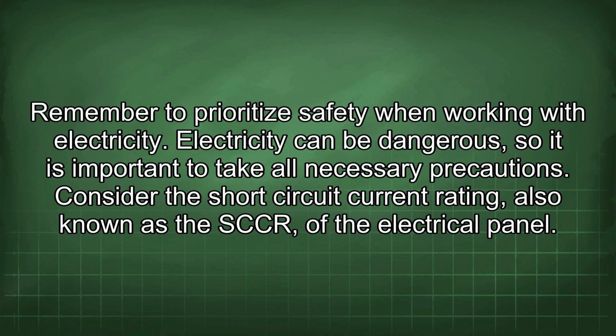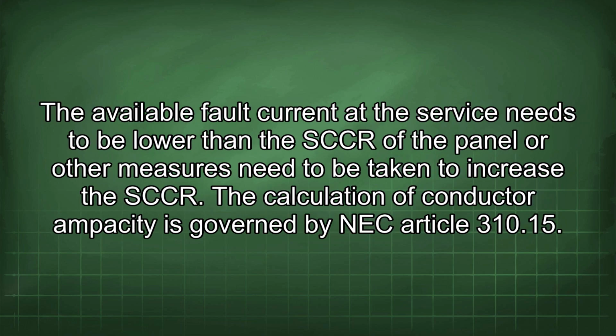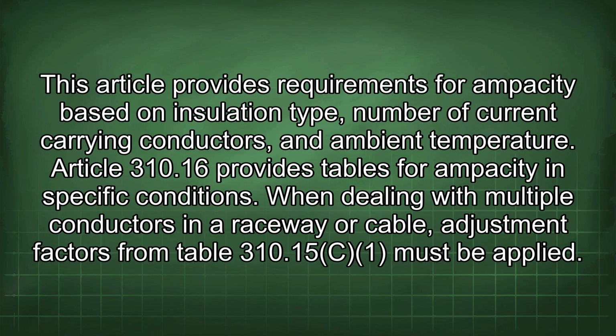Consider the short circuit current rating, also known as the SCCR, of the electrical panel. The available fault current at the service needs to be lower than the SCCR of the panel, or other measures need to be taken to increase the SCCR. The calculation of conductor ampacity is governed by NEC Article 310.15. This article provides requirements for ampacity based on insulation type, number of current carrying conductors, and ambient temperature. Article 310.16 provides tables for ampacity in specific conditions.